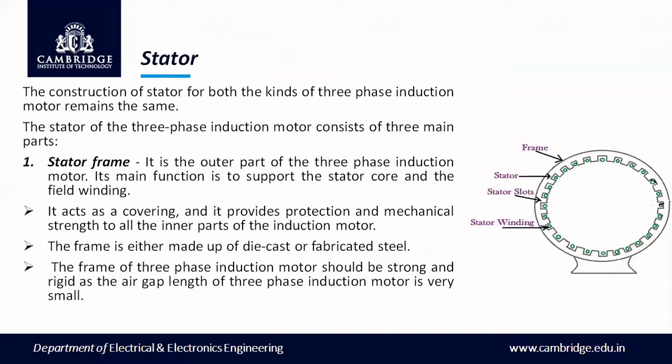The frame of a three-phase induction motor should be strong and rigid, as the air gap length of a three-phase induction motor is very small. Between the stator and rotor, the air gap length is very small. That is why the frame of this induction motor should always be very strong and rigid. Strong and rigid means it should be able to withstand any mechanical or environmental conditions, and from all those conditions, it should be able to protect the motor. That is the function of this stator frame.